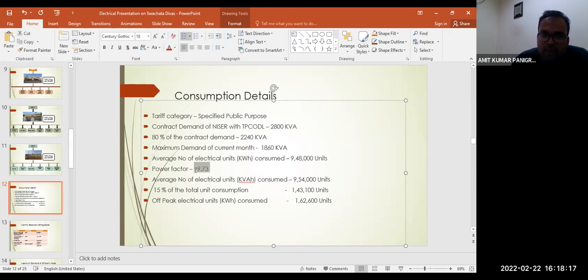Here we see that the power factor we have maintained is 99.73. So the average electrical unit in kVAh is coming to 9,54,000. Our bill is based on the kVAh consumed, not kilowatt hour. If our power factor becomes 1, then our kilowatt hour and kVAh become equal. So if our power factor is 1, then our units bill will not be 9,54,000, it will be 9,48,000.